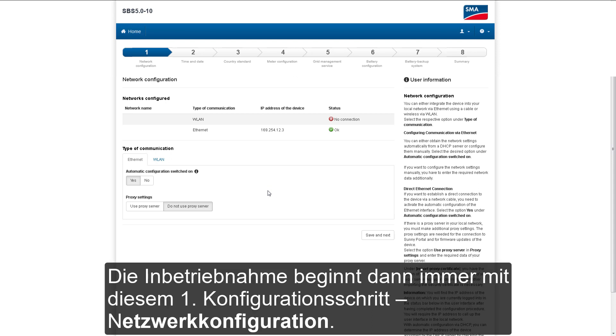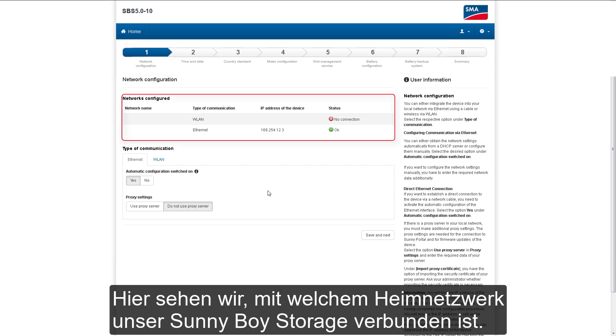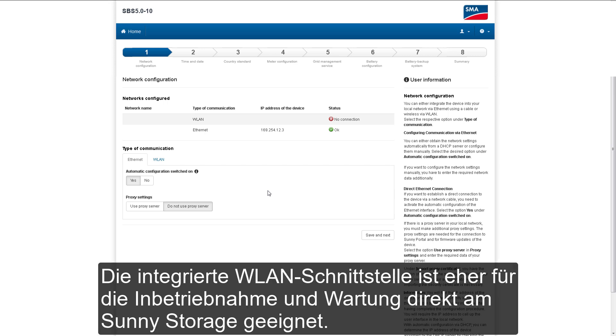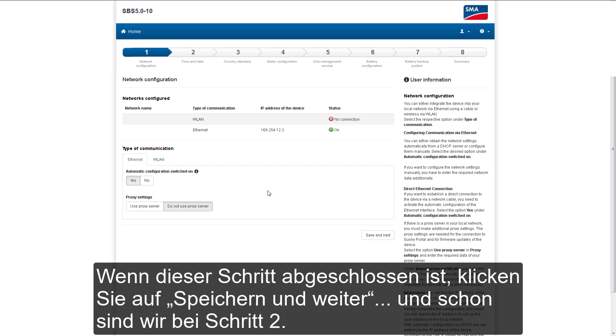Commissioning always starts with the first configuration step: Network Configuration. Here we can see which home network our Sunny Boy Storage is connected to. For initial configuration, please always try to use the wired version based on Ethernet. The integrated wireless LAN interface is more suitable for commissioning and maintenance purposes directly at the Sunny Boy Storage. Once this setup is done, click Save and Next in the bottom right corner to go to step two.